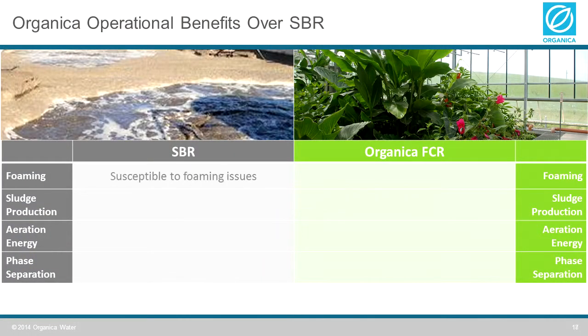As SBR is a suspended growth system, it has similar issues that you would normally face in a conventional activated sludge treatment plant, like sludge bulking and foaming. Sludge bulking actually is more prominent in SBRs since the active biomass goes for a considerable period without food during the settling and the decanting phase.